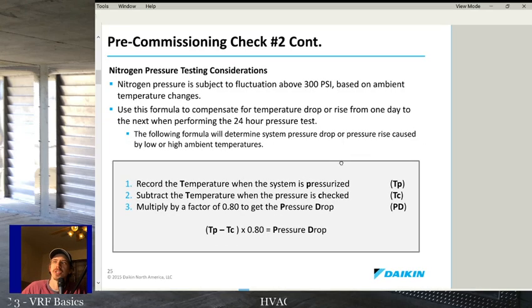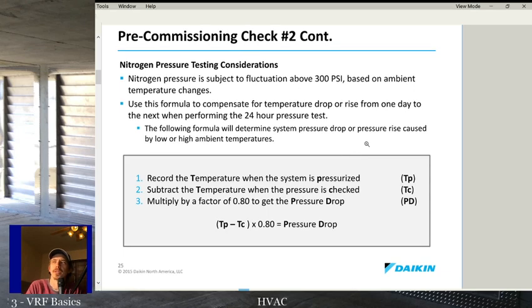This is a pretty good cheat sheet on knowing the pressure difference that you're going to have after a temperature difference with nitrogen. Above 300 psi, you're going to have noticeable fluctuations. Under 300 psi, the pressure change is usually small enough that you probably won't notice it anyway. Unless you have a very accurate gauge, you're probably not going to notice the pressure changes with the temperature below 300. But once you get above 300, you've got such a large amount of pressure in there, the temperature changes are going to affect it more.